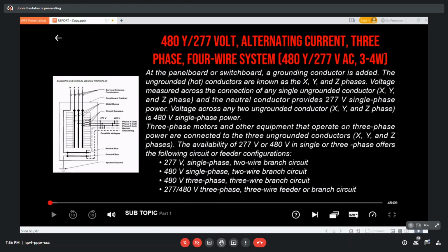When compared with the 208/120 volt system, the 480/277 volt system has an economic advantage from the standpoint of equipment and conductors, because a given conductor can carry more than twice the load at 480 volts than at 208 volts. The savings in wire size for feeders can be quite significant.